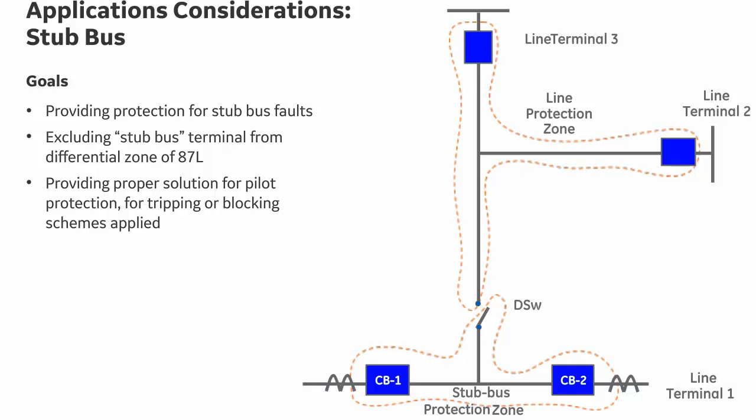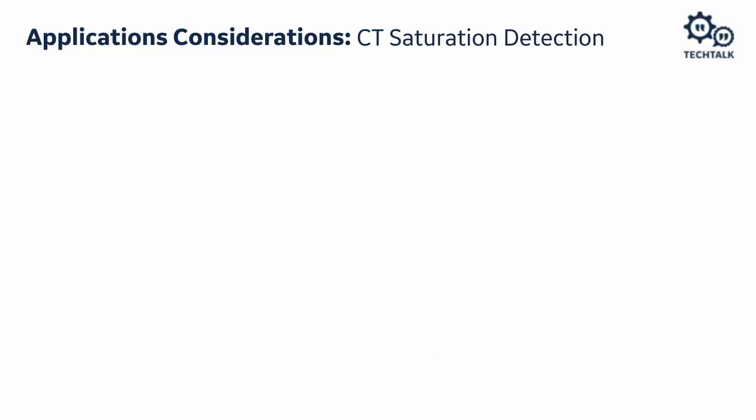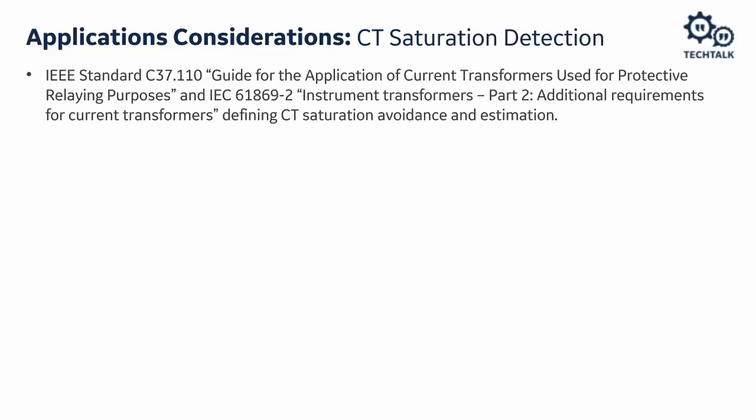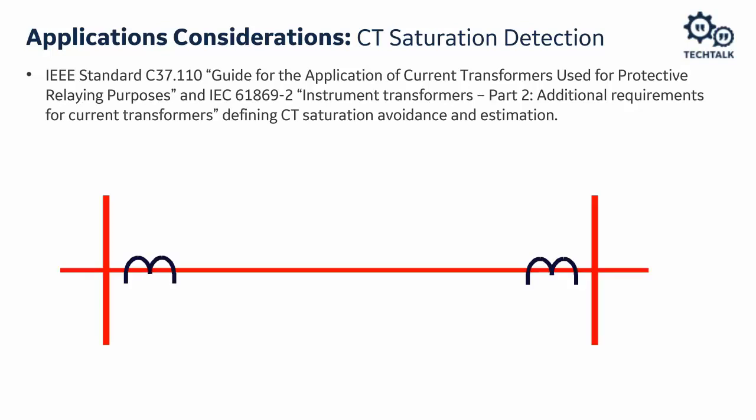For CT saturation, we have IEEE standard C37.110 — a guide for application of current transformers used for protective relaying — and IEC 61869-2, additional requirements for current transformers, defining CT saturation avoidance estimation. It is desirable to avoid saturation, but it's not always possible and requires increasingly expensive and larger CTs. When we have internal faults, CT saturation does not cause a problem, but when we have external faults with asymmetrical CT saturation, it may be a problem.